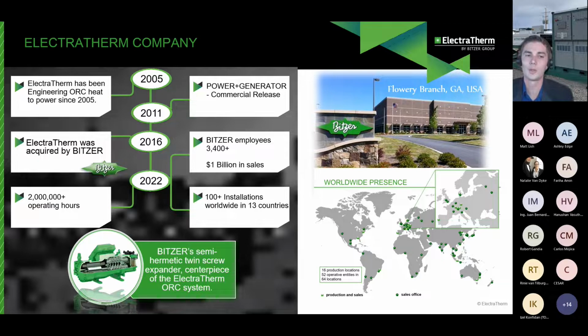We're a solution provider, but we're also large enough with Bitzer ownership and support that we can support all of these units in even some of the most remote of locations. Bitzer's semi-hermetic twin screw expander is actually the centerpiece of our ORC system. So it's based on refrigeration compressors. And in that sense, our equipment is more similar to an appliance rather than a power generation device. Although what we're making is power, in regards of operation and maintenance, this is more similar to your refrigeration type appliances.